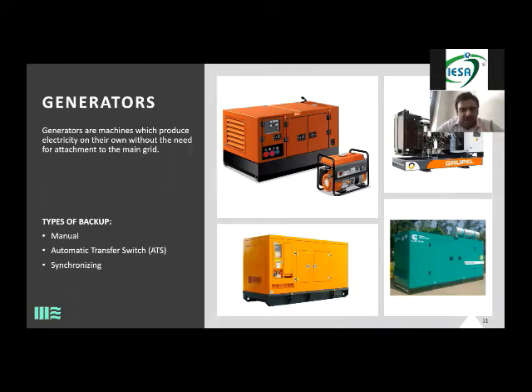Okay. I'm just taking two before we proceed. Can you list out the HSSE parameters for a genset during operation, and before and after operation? The parameters are very normal. As I told you, if you check the manufacturing and maintenance records, I think most of that is done. But when the genset is coming on site, there is a physical check. In the starting slide, I showed you some pictures which you look at and feel are absolutely unsafe. Same with the genset. When it comes on site, if you open the doors and there is any oil leakage on the ground at the base of the genset, automatically it is not right. The genset has to be absolutely clean. The engine has to be right. You can check the air filters and the oil filters. Just like when we take our car to the petrol pump, we tell them to check the engine oil, the engine also has to be checked like that.